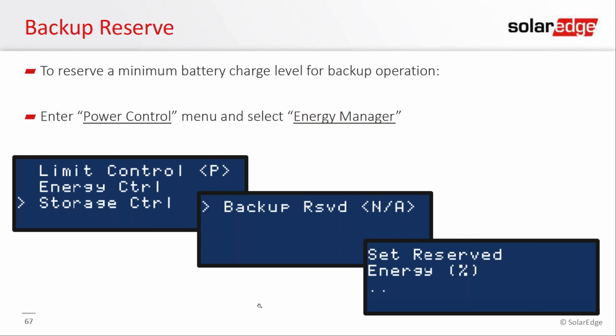That's a question we always get. Can I do off-grid? So the SolarEdge answer is no. We don't do off-grid. This is intended as a grid-connected battery, and that's how we want to use it. Does that mean that people haven't done off-grid? No, there are people that have done it. Puerto Rico is a great example. They suffered a lot of damage from the hurricanes, and StorEdge is going in there like hotcakes because it's an awesome product, and they're still 20% on the island. There's still no grid connected, so they're finding ways to set up the inverter and to have it run as a quote unquote off-grid inverter. But in general, that's not recommended, and we always recommend it to be grid tied.